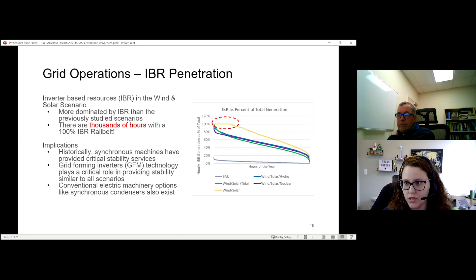Historically, synchronous machines, the generators for conventional generation, are critical for stability because they provide inertia to the system. Once we retire these machines, we have less inertia in the system, meaning a weaker system. So in a context with a lot of inverters, we have a weaker system and it complicates our stability. However, we have new technologies emerging, like grid-forming inverters, that help a lot with stability. We can also apply conventional machinery like synchronous condensers to keep stability in the system.